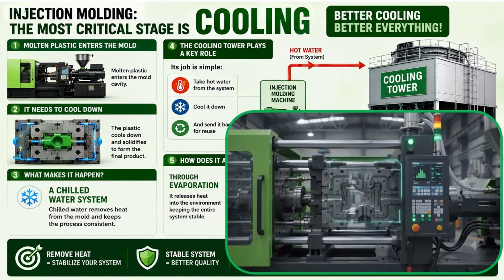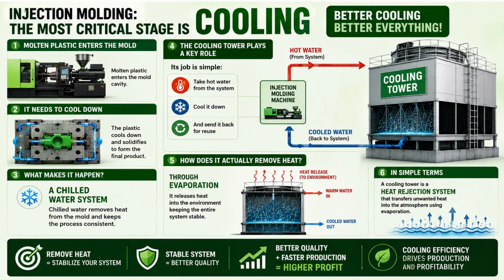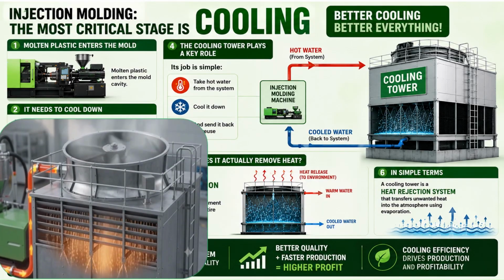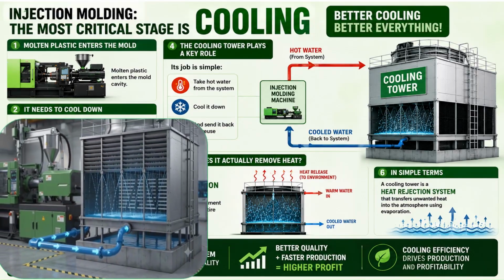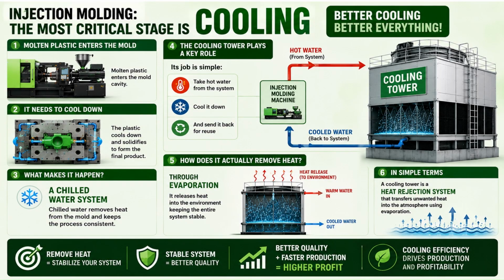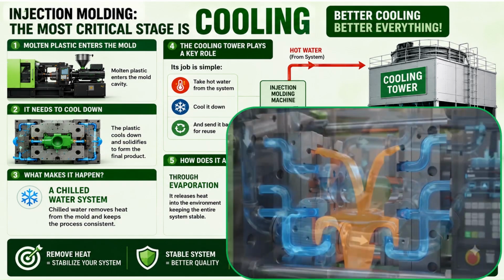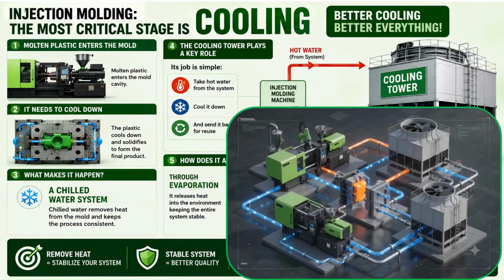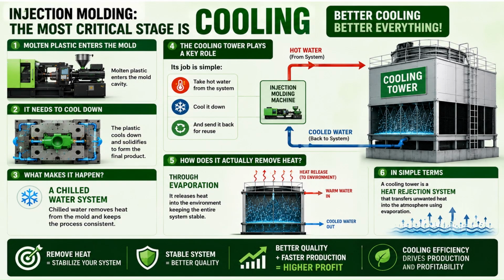In injection molding, the most critical stage isn't filling, it's cooling. Once molten plastic enters the mold, it needs to cool down and solidify properly. And what makes that happen? A chilled water system. Now here's where it gets interesting, the cooling tower plays a key role. Its job is simple: take hot water from the system, cool it down, and send it back for reuse. But how does it actually remove heat? Through evaporation. It releases heat into the environment, keeping the entire system stable. In simple terms, a cooling tower is a heat rejection system that transfers unwanted heat into the atmosphere using evaporation. Remove heat, stabilize your system. Stable system, better quality plus faster production.